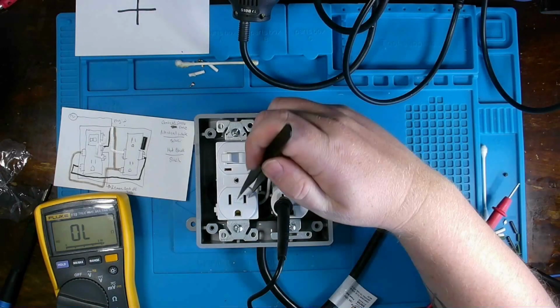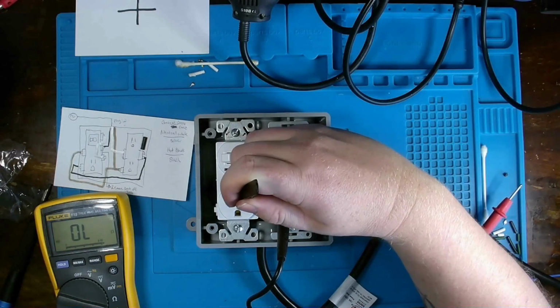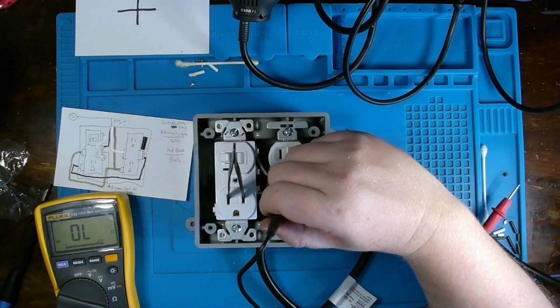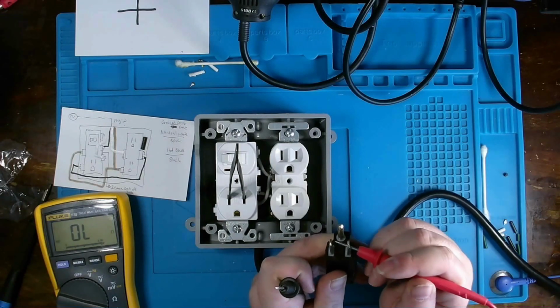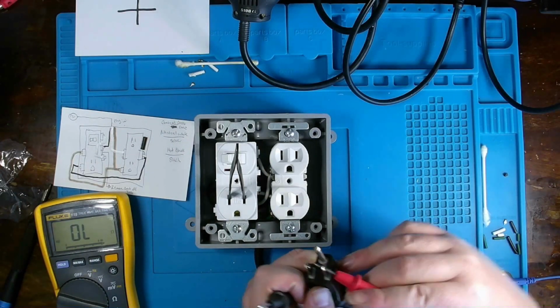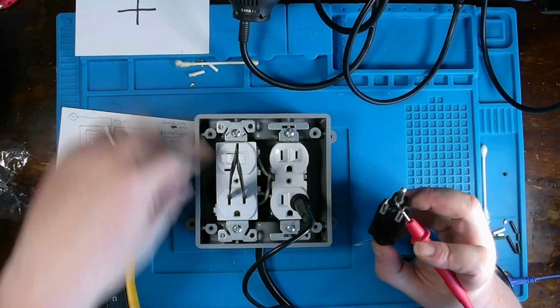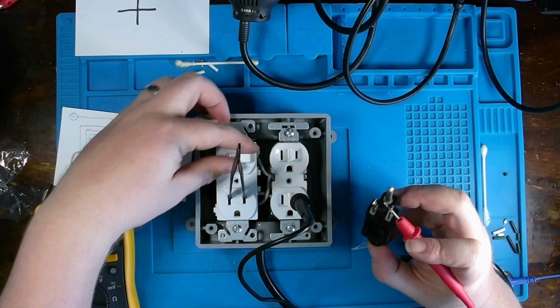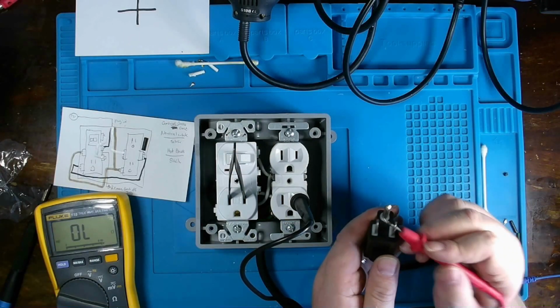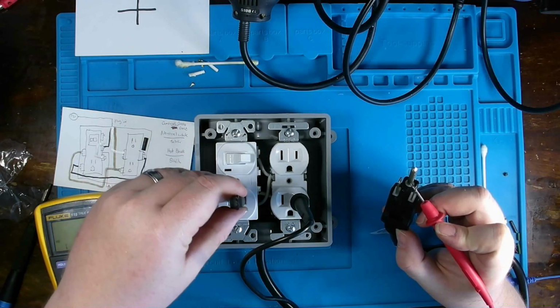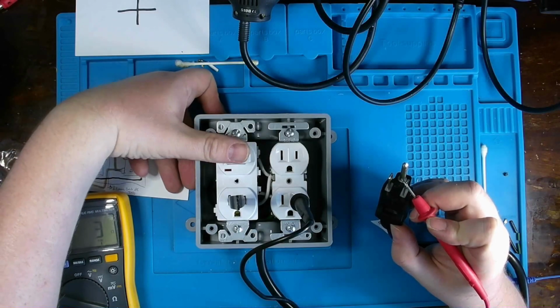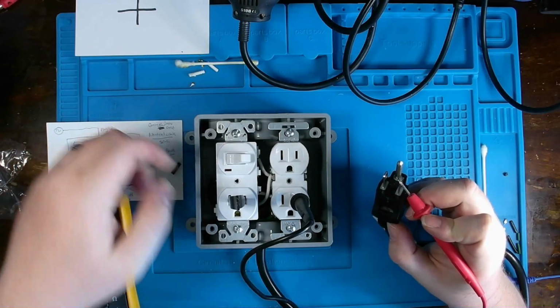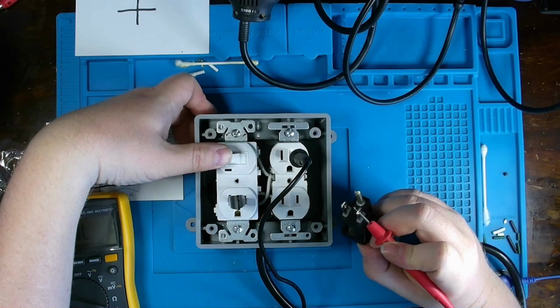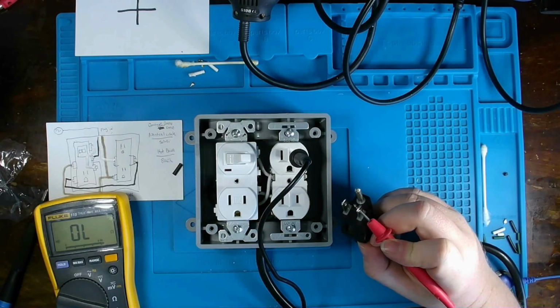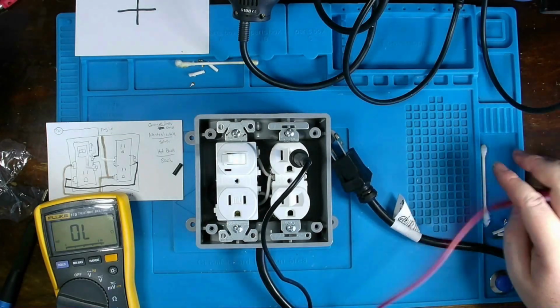Next is going to be the hot. Now again, I'm going to short out inside this plug. And now I'm going to go to the hot lead, that is the far right lead, and plug this into my hot. With off, there shouldn't be continuity, with on there should be. Okay, let's try that again: off, on, off, on, off, on, off, on. Now if I remove that short, it should also disappear. So if all these test good, we should be good to go.